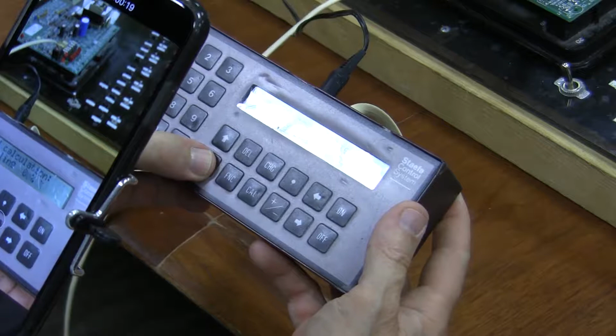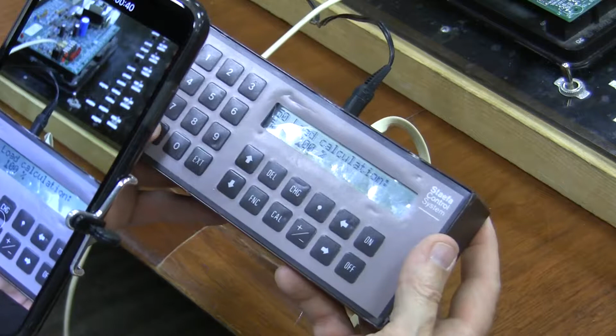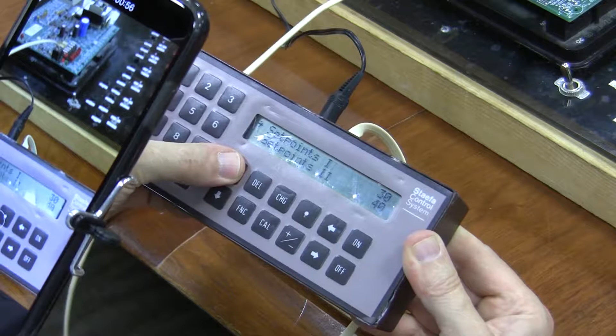So I'm going to hit enter on 100% cooling, and now I get a scroll and say, what value cooling do you want to make? I could make it 2% cooling, 98%. I'm going to actually say, go to 100% cooling, and I'll hit enter. So now we just manualed that card at cooling. We're going to go back and look at it in the 20s and see if it got it. Okay? We're going to go back here. We're going to scroll by the 10s.